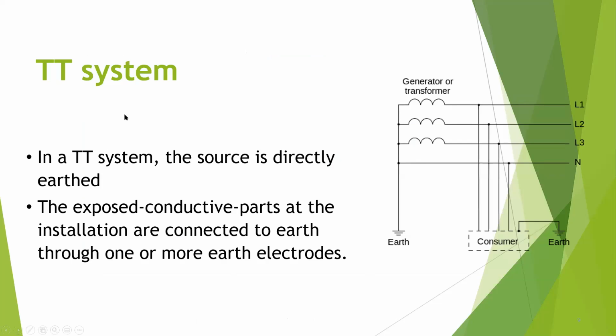Okay. So as mentioned before, in the TT system, the source is directly earthed, and the exposed conductive parts at the installation are also earthed through one or more earth electrodes. So that means we are trying to reduce our earth electrode resistance, because when you have more electrodes we have more parallel paths for the current to flow. So you are reducing the earth electrode resistance, so the harm done to your human body will be lower when you have a low earth electrode resistance.